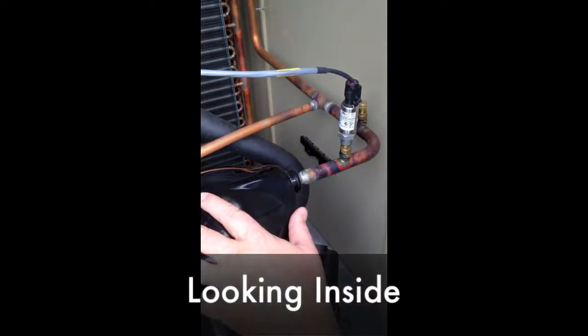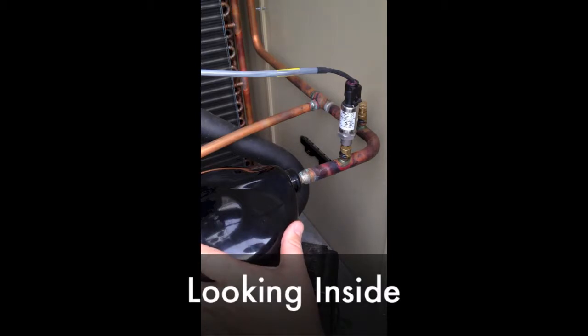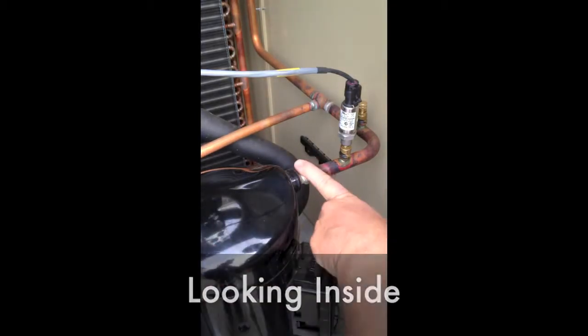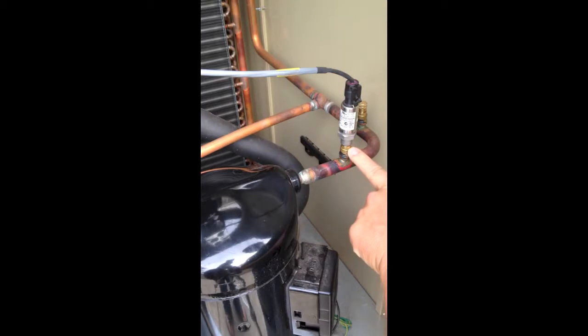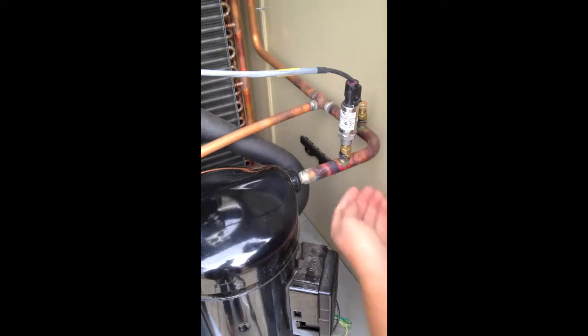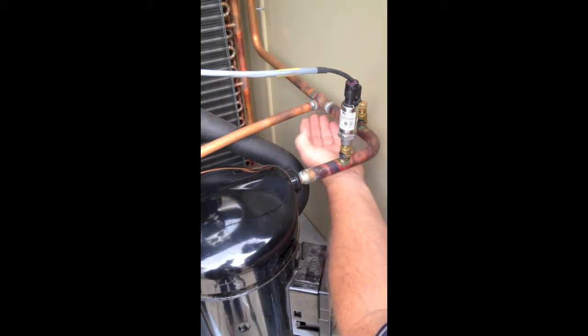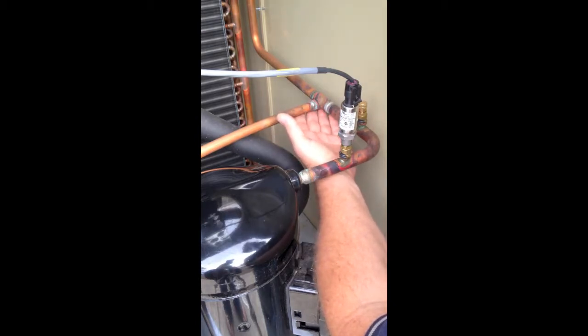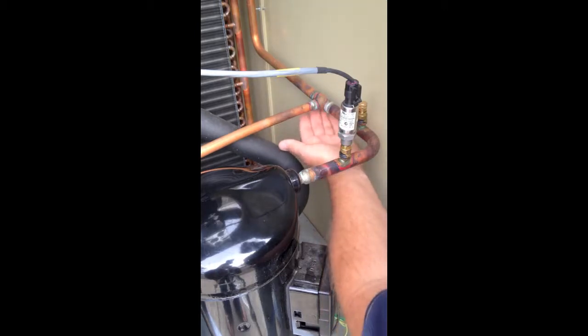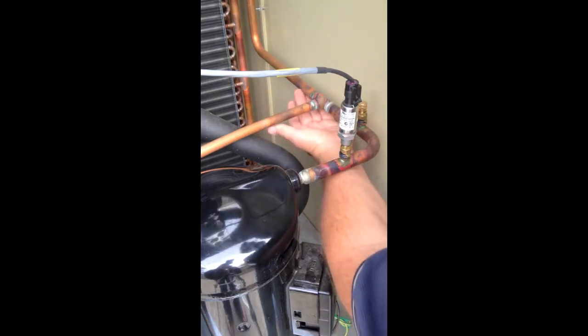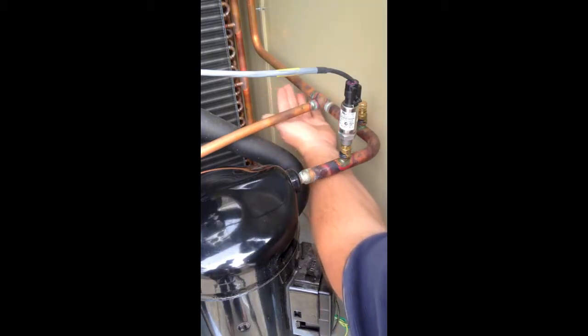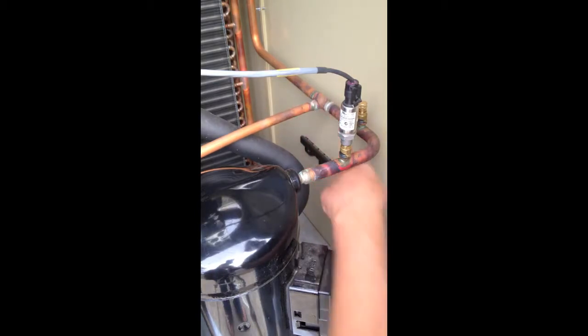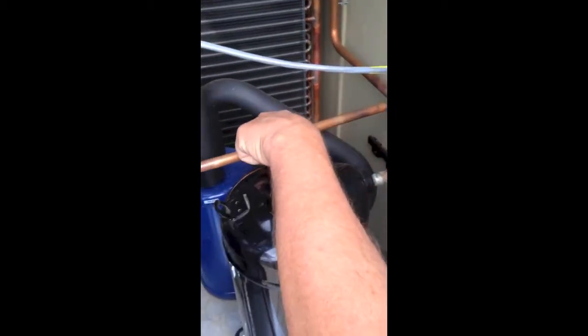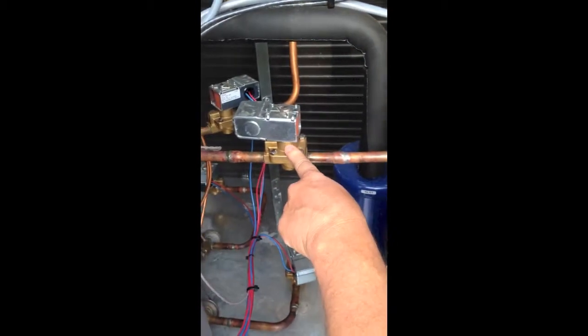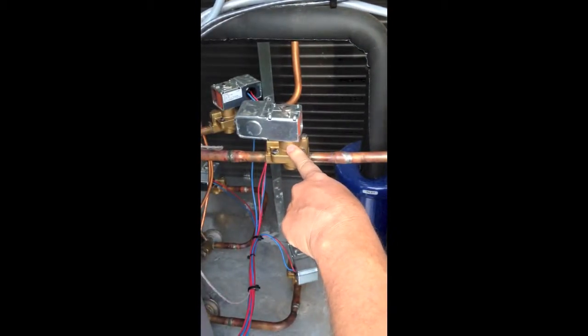So what we're looking at here is the top of our Copeland scroll compressor. This is our discharge line. This is our high pressure transducer, our service port. Now right here is a critical junction. As I mentioned earlier, hot gas bypass is standard on all scroll model chillers. One direction that the high pressure gas goes off to is the inlet of our condenser. The other branches off over here. If you follow this pipe along here, it takes us right to our hot gas bypass solenoid valve.